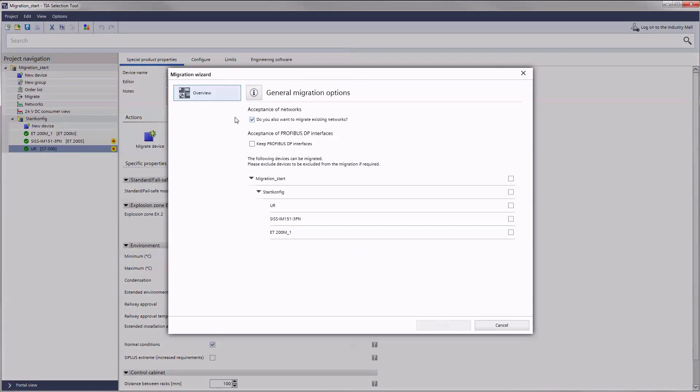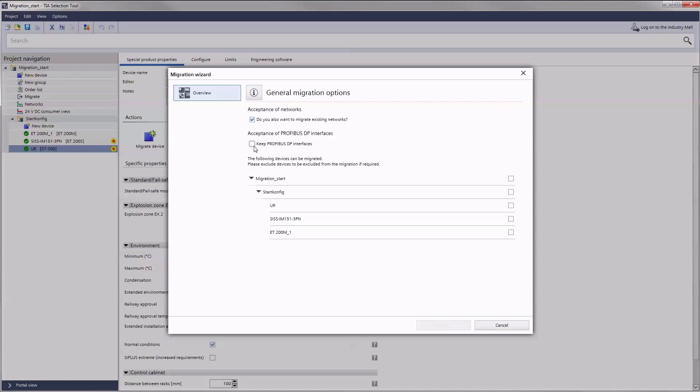In the general migration options first select whether you want to migrate existing networks. The new devices are then automatically linked with each other. If you would like to keep existing PROFIBUS DP interfaces check the corresponding box. If the option is not selected the PROFIBUS connections are automatically converted into PROFINET connections.